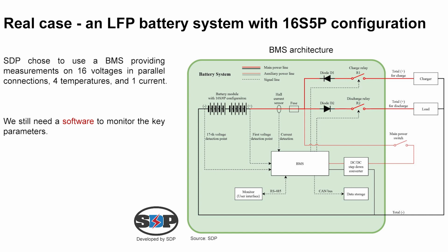The auxiliary power of the BMS is obtained from the DC-DC step-down converter, which converts the high-voltage power to the low-voltage auxiliary power. The main power switch is used to control the power on-off of the whole battery. When the main power switch is off, there is no auxiliary power passing through the BMS, and the charge and discharge relays are off. The BMS is under shutdown mode, indicating almost zero power consumption. Meanwhile, there is no current in and out through the battery system. When the main power switch is on, the auxiliary power passes through the BMS, and the charge-discharge relays are turned on and monitored by the BMS. This is the normal mode and the current can go in and out through the battery system.